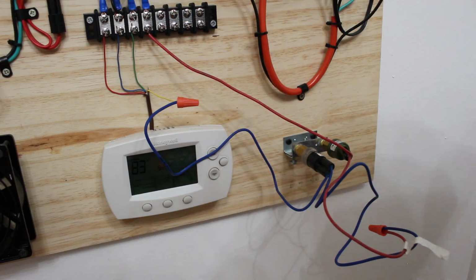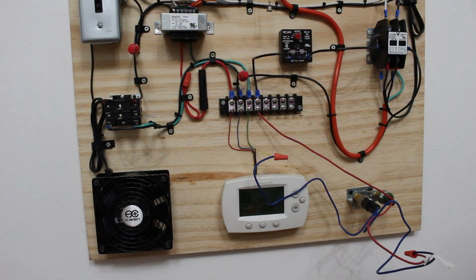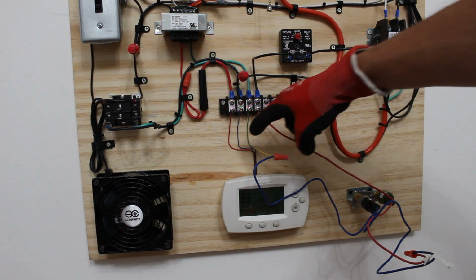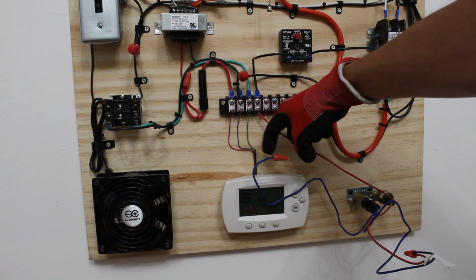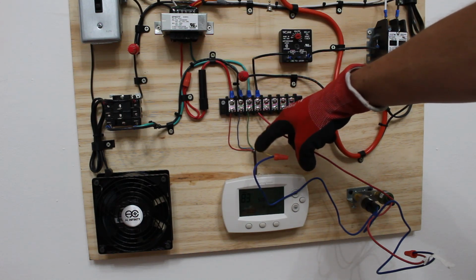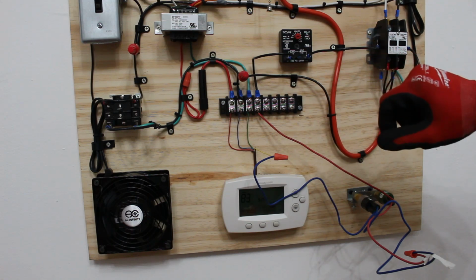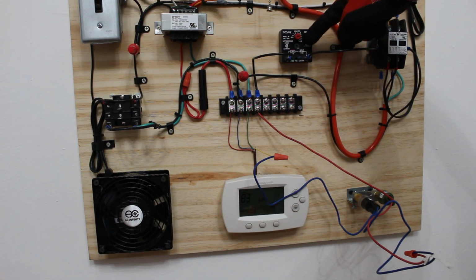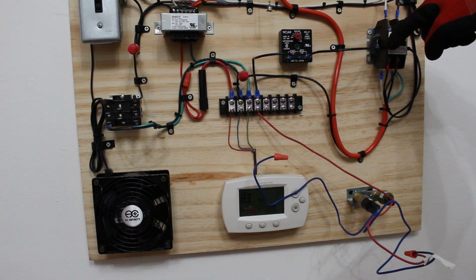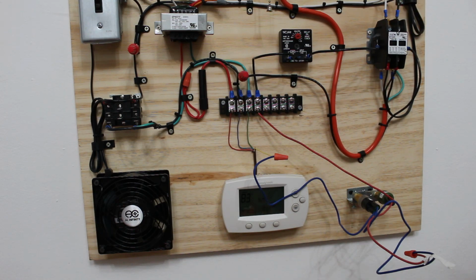So let's explain exactly the flow of operations here. We get a call for cooling. So what's gonna happen is that now the yellow wire, which is our cooling wire, before it can go to all of our components, in this case we have a timer and a contactor, what's going to happen is that we're now going to go through our safety controls.